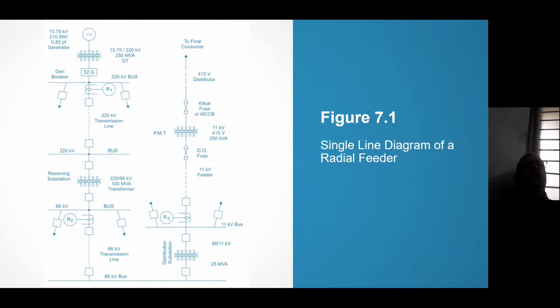Right? Similarly, 2 is for timer, 27 is for under voltage relay, 51 is for time delayed overcurrent relay, 50 is for instantaneous overcurrent relay, 21 is for distance relay, 29 is for isolator, 98 is for pole slipping relay, 99 is for fluxing relay. Like that, standard numberings are decided internationally so that everybody will understand. And in drawing also it is easier to write 52G, rather than writing that big thing generator breaker.